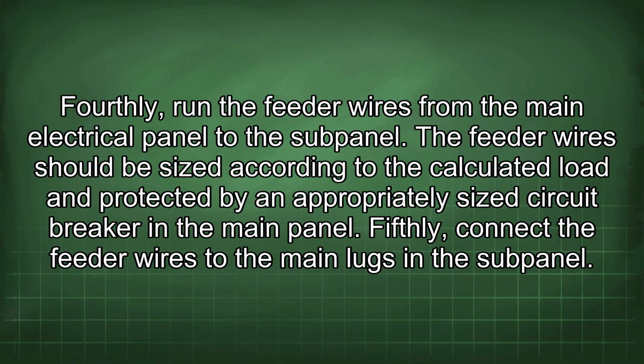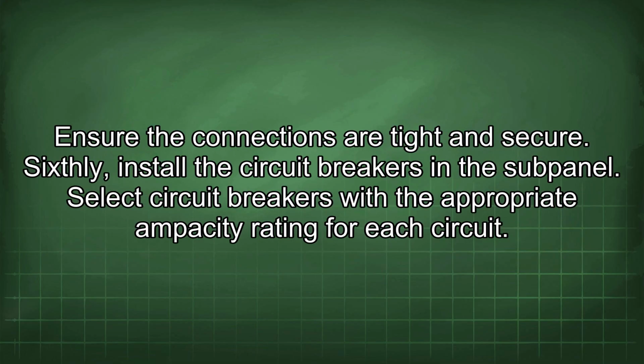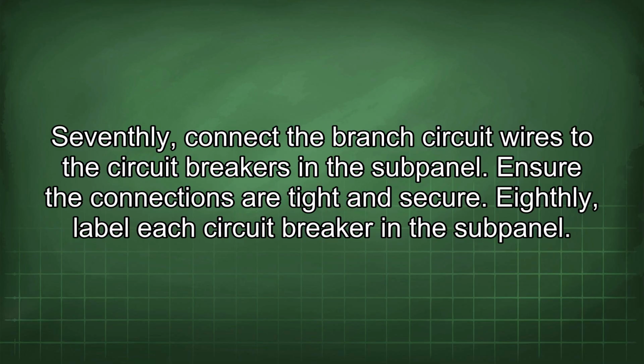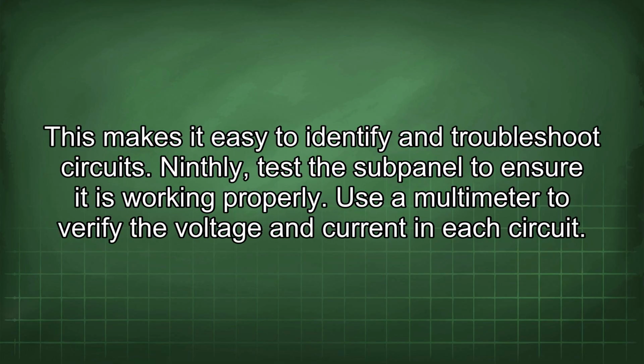The feeder wires should be sized according to the calculated load and protected by an appropriately sized circuit breaker in the main panel. Fifthly, connect the feeder wires to the main lugs in the subpanel. Ensure the connections are tight and secure. Sixthly, install the circuit breakers in the subpanel. Select circuit breakers with the appropriate ampacity rating for each circuit. Seventhly, connect the branch circuit wires to the circuit breakers in the subpanel. Ensure the connections are tight and secure. Eighthly, label each circuit breaker in the subpanel. This makes it easy to identify and troubleshoot circuits.